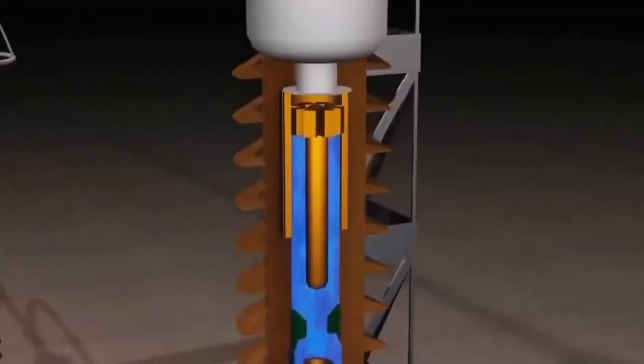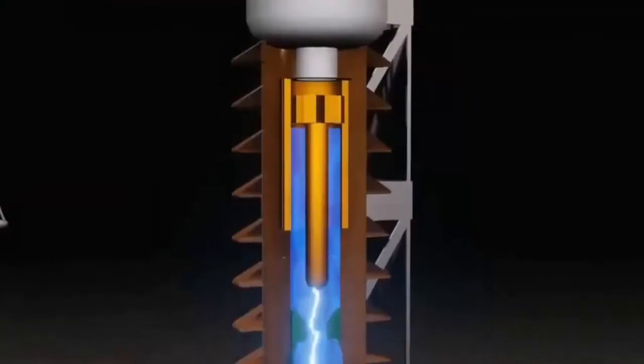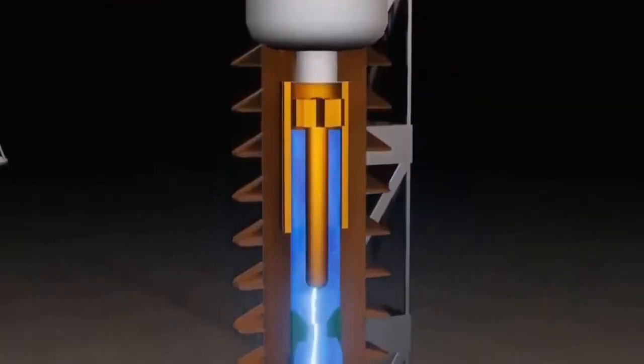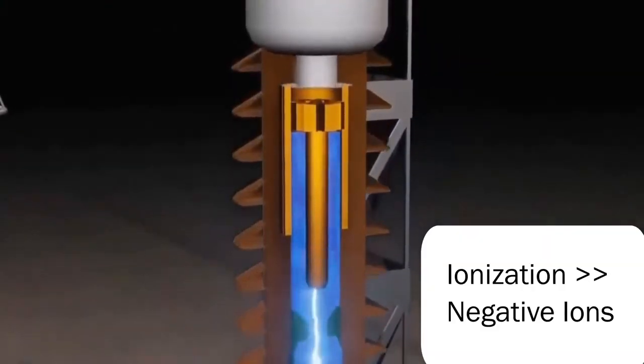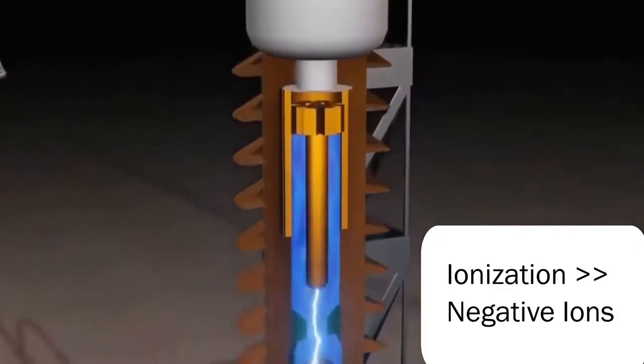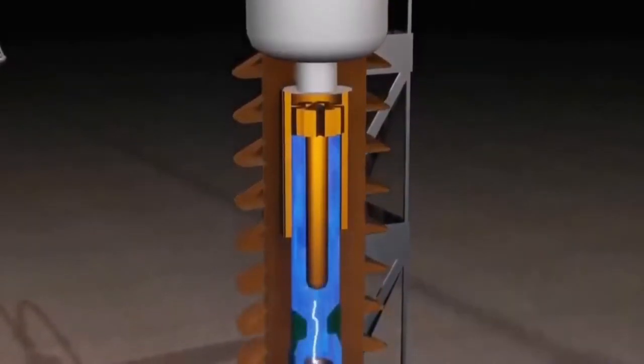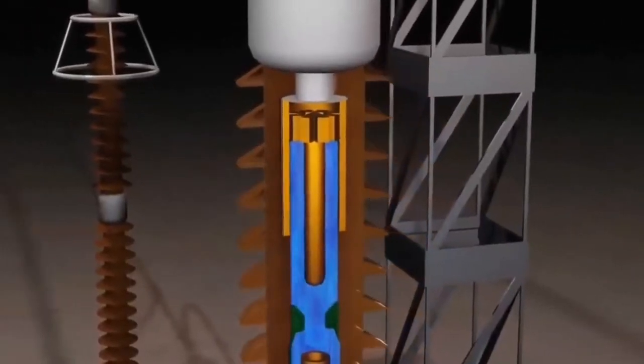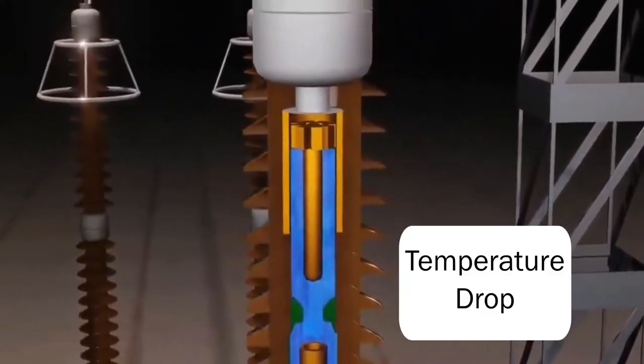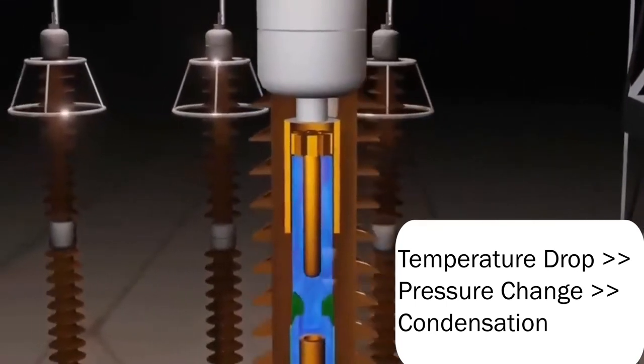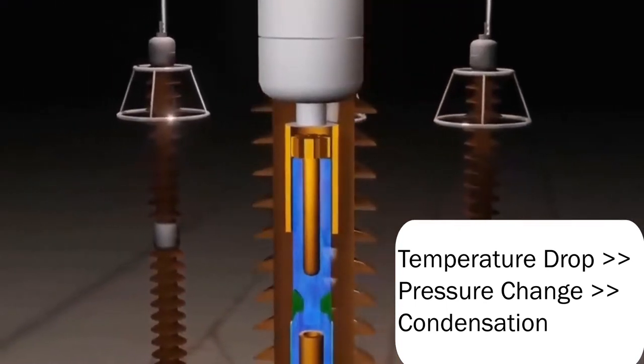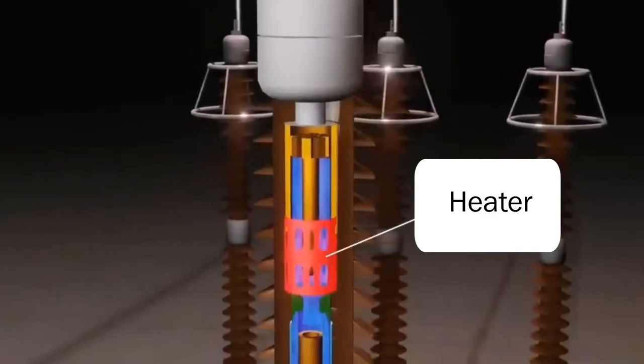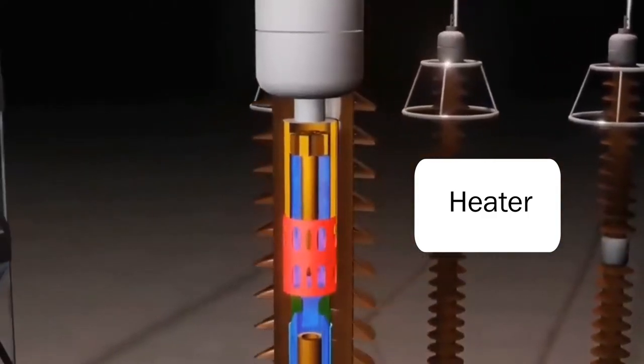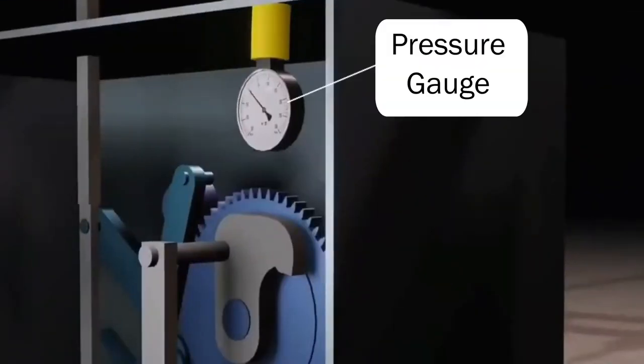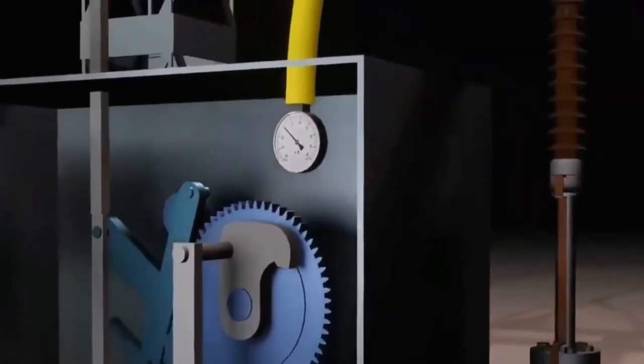How does sulfur hexafluoride extinguish the arc? Sulfur hexafluoride is able to extinguish the arc because high temperatures cause it to ionize into negative ions, which prevent free electrons from moving and thus eliminate the arc. However, there is an issue. After the arc is extinguished, the temperature inside the circuit breaker decreases, and under certain pressure, sulfur hexafluoride will transform into a liquid. At this position, a heater is also needed to ensure that SF6 remains in a gaseous state. Of course, SF6 will also be consumed, so a pressure gauge is installed at the top of the circuit breaker to replenish the gas once the pressure drops.